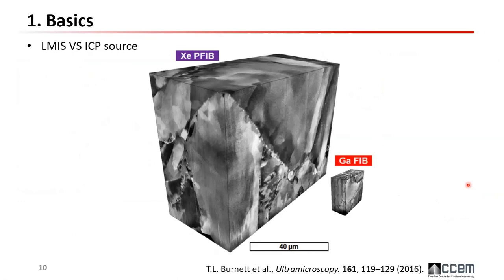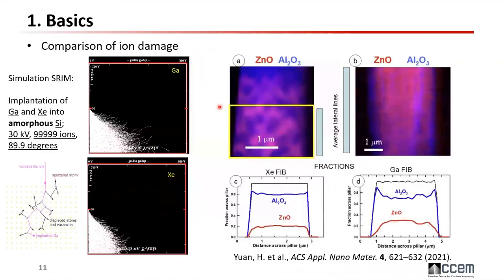One thing that comes to mind is the milled volume: the xenon source is much larger and allows access to big volumes, giving you good statistics for your sample. Another advantage of xenon is less ion damage. Simulation shows the impact between the ion beam and the sample — even if the simulation is for amorphous silicon, it gives you an idea of how deep the damage goes with each source type. The xenon damage is shallower.